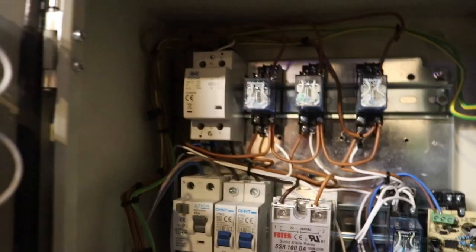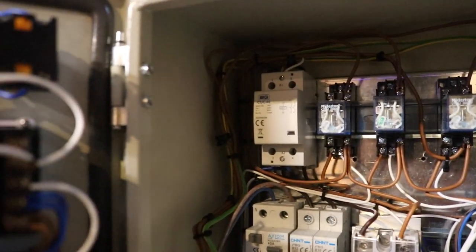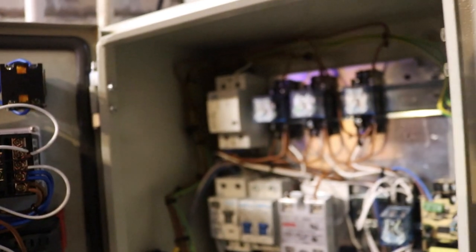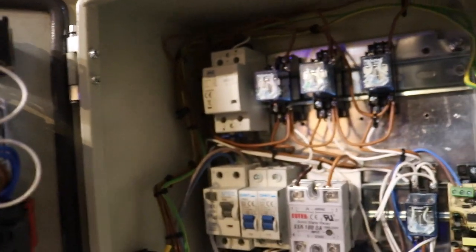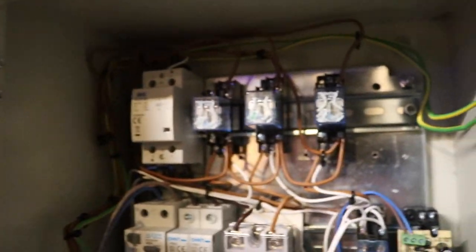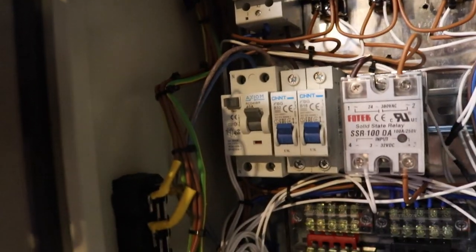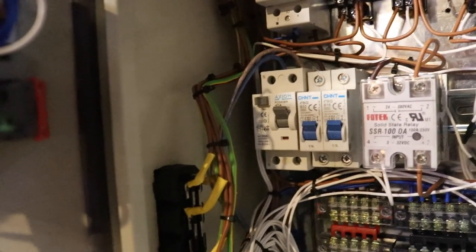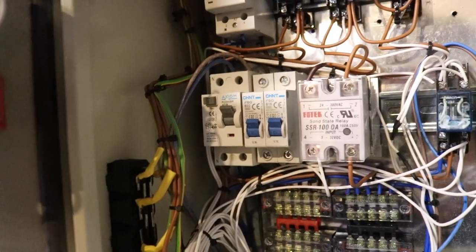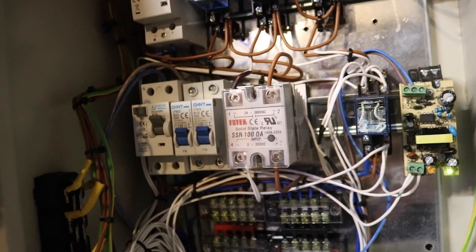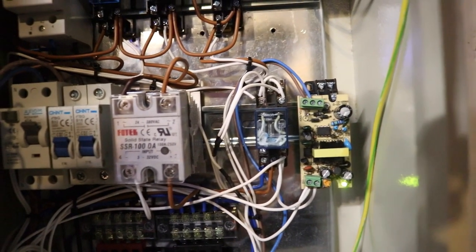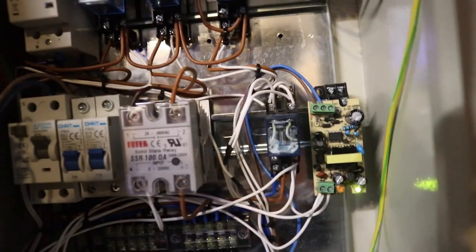As you can see everything is in place. So from top left to bottom right we've got a relay which is operated by these three interlocks here to allow us to let the countdown timer run down before we send any power to the pumps. Then we've got pump one, pump two, and pump three relay. Next row down we've got the mains RCD residual current device and then two MCBs overload protection. Then we've got the solid state relay for the heating element.